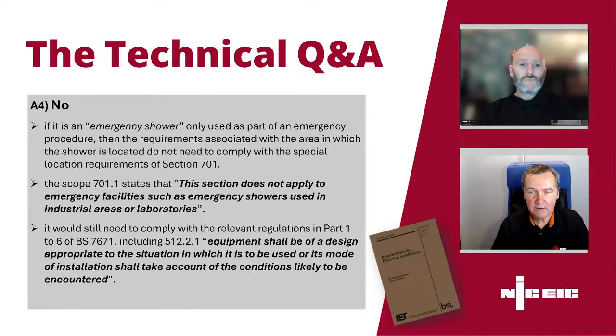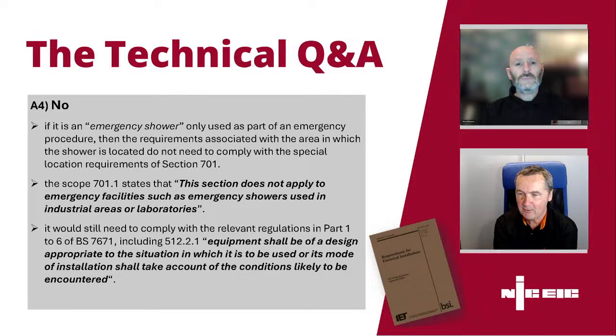Yeah, and that's on the basis that it's a different situation to a traditional shower, a domestic shower, where people are going to be completely unclothed, probably unsupervised. Now we're talking about a workplace emergency shower where people will be clothed. There will possibly be other people involved. So we've got a whole different scenario, and the perceived risks of electric shock are very different. And the shower's not going to be frequently used, so the electrical hazards and the protection against those hazards don't need to be as onerous as for your typical domestic shower or general shower, which is frequently used. So that's why it's treated differently, because although it's a shower, it's for a completely different purpose, and therefore the perceived risk of electric shock is very different.